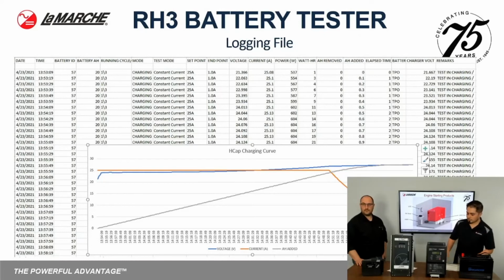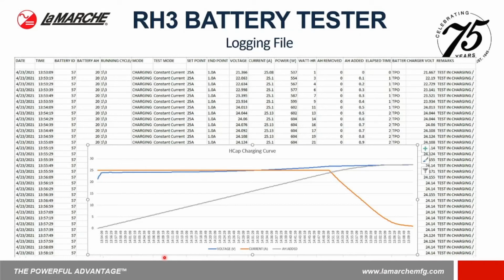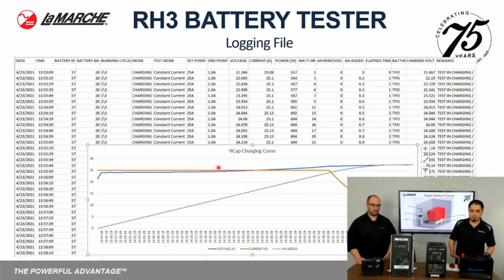Just a quick overview of what it looks like on the actual Excel file. As you can see here, you have your most important parameters being your date, time, your ID. Obviously, you can set up different batteries for this. Battery amp hours, your running cycle, your actual testing mode, charging or discharging, your set points, endpoints, voltage, currents, and all that good stuff. Just also show that quick diagram here of how easy it is to go ahead and set up a quick trend line just with those data points from that one charging or that one discharge cycle. It's very easy to go ahead and see a trend or set up a continuous or monthly cycle to see how it keeps trending either upwards or downward in your system.